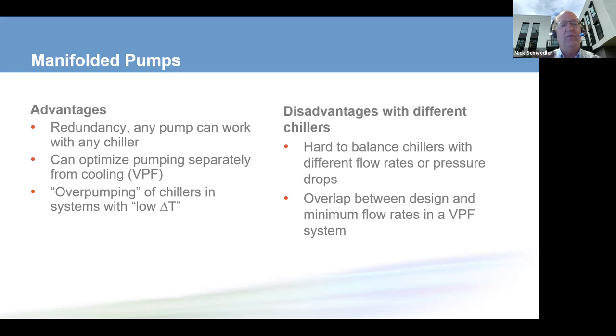So now we have to do some gymnastics from a system control standpoint by opening the valve in the bypass line to maintain the minimum flow rates for all the chillers. So it does become harder to get proper sequencing in a variable primary flow system if we have different capacity chillers. So those are some disadvantages.